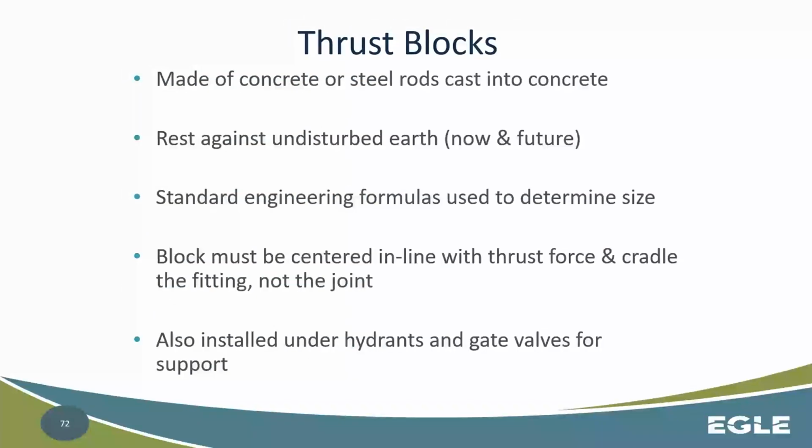No. Okay. Thrust blocks. So made of concrete or steel rods, cast in concrete. So it's all kind of depending on the situation that you're doing. Rests against undisturbed earth. Again, we already kind of just talked about that, making sure that pressure is being released into that compacted soil to disperse it as best as possible. Standard engineering formulas are used to determine the size of the actual thrust blocks themselves. They should be centered in line with thrust force and cradle the fitting.